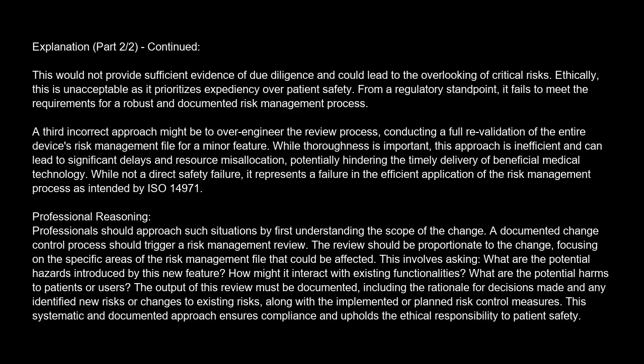The review should be proportionate to the change, focusing on the specific areas of the risk management file that could be affected. This involves asking, what are the potential hazards introduced by this new feature? How might it interact with existing functionalities? What are the potential harms to patients or users? The output of this review must be documented, including the rationale for decisions made and any identified new risks or changes to existing risks, along with the implemented or planned risk control measures. This systematic and documented approach ensures compliance and upholds the ethical responsibility to patient safety.